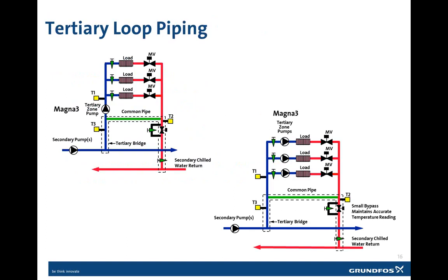Now, one main difference with the tertiary loop piping is that not all the zones or buildings are operating the same. So the tertiary pipe systems provide the ultimate flexibility for the design and the operation of the individual zones or buildings. The common pipe hydraulically isolates each system, so at no time is an individual building dependent on its neighbor. Then the individual supply water temperatures can be achieved and maintained, and the head required for each building's pump is also independent rather than running on common pumps. The pumps for the individual buildings are then calculated as if no other building is involved in the system. Then the secondary pumps are relieved of the head required to serve the entire individual building.